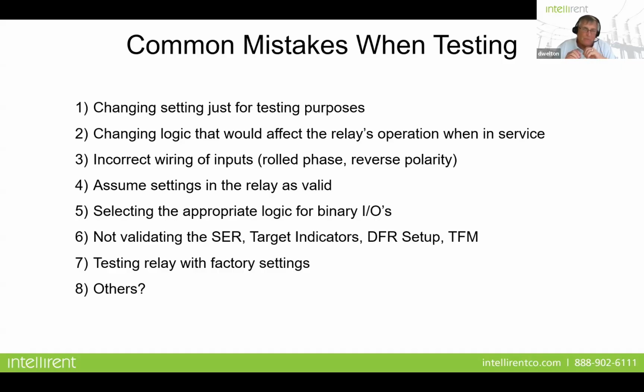Okay, so a couple of common things when you're testing relays that I think are really important. Number one, don't change the settings just for testing purposes, and I saw this on the old electromechanicals. They'd be doing a BDD or an HU relay, and they'd put the tap values on 1 amp or put them on 5 amps and test the slope that way, because nobody wanted to do the math to apply the right per unit values. Well, this happened at Dow Chemical many years ago, and the guy took the HU out of service, moved the taps, tested the relay, put it back into the rack, closed in the CTs, PTs, and trip contacts, and took the substation out of service because he forgot to put the taps back. Okay, so don't go changing your settings.